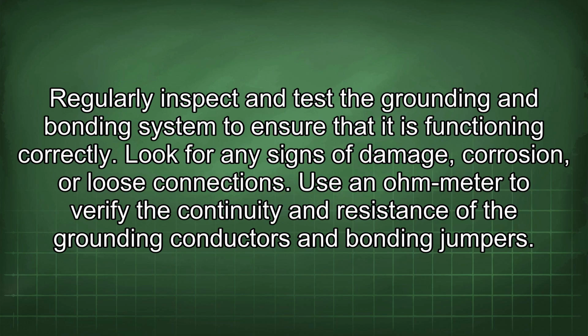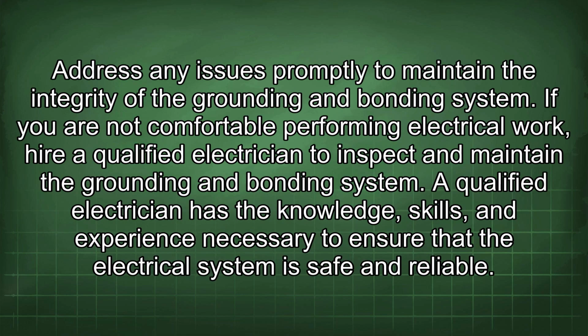Regularly inspect and test the grounding and bonding system to ensure that it is functioning correctly. Look for any signs of damage, corrosion, or loose connections. Use an Ohm-Meter to verify the continuity and resistance of the grounding conductors and bonding jumpers. Address any issues promptly to maintain the integrity of the grounding and bonding system.